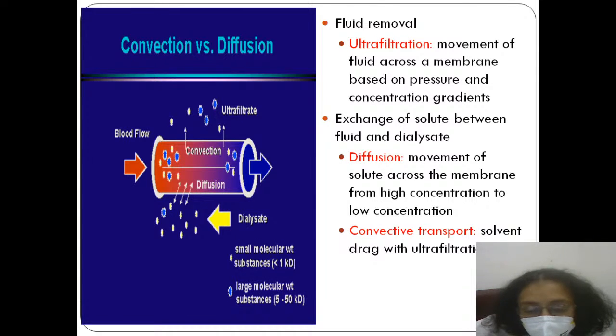It occurs by diffusion mainly, where there is movement of solute across the membrane from high concentration to low concentration. This blood in the tube has a higher creatinine and urea level because the patient has kidney failure, while the dialysate fluid here has no urea or creatinine. Since the concentration is higher over here, the urea and creatinine will diffuse out into the dialysate fluid, so the blood gets cleaned out. The second thing that happens is convective transport. When you are applying pressure to cause ultrafiltration, as the fluid gets pushed out, it also drags solutes out. The solutes dragged out are usually those which have a smaller molecular size compared to the solutes which have larger molecular size. So fluid removal is mainly by ultrafiltration, while solute removal is by diffusion as well as by convective transport.